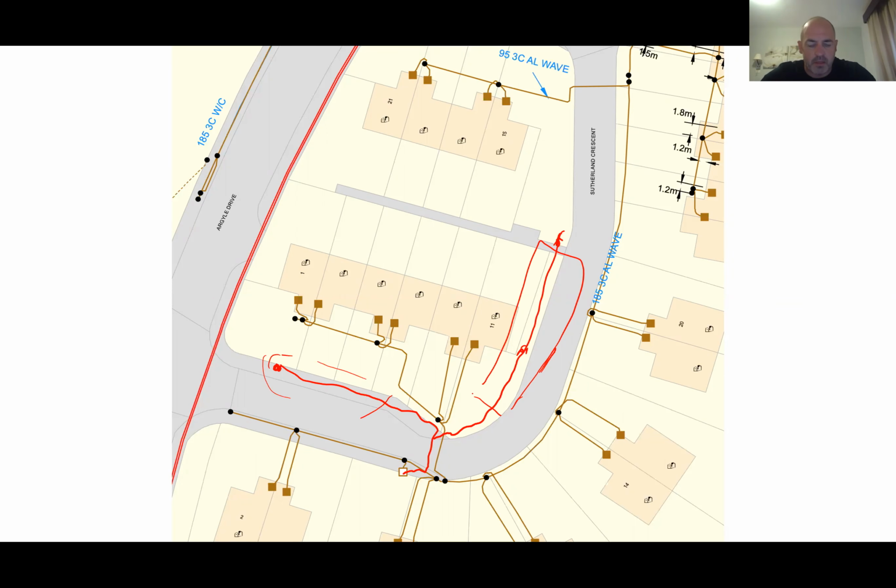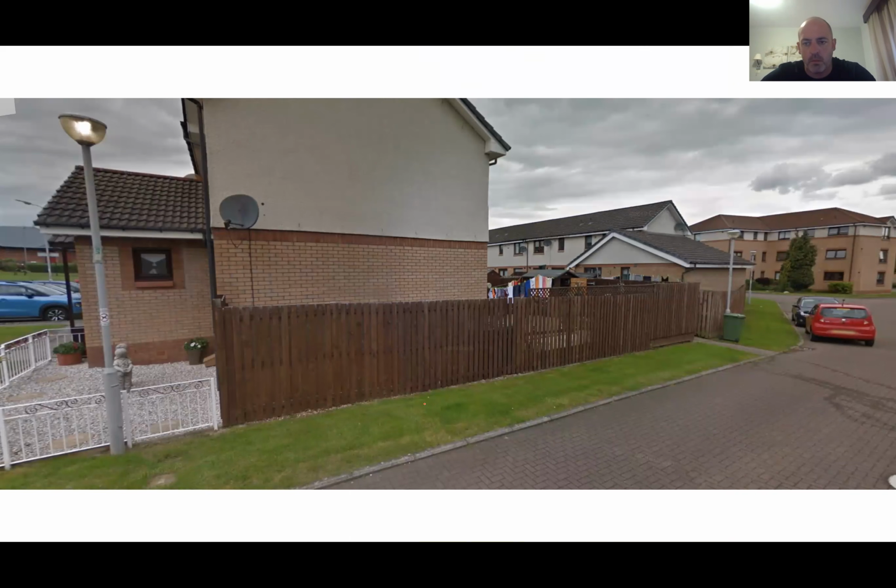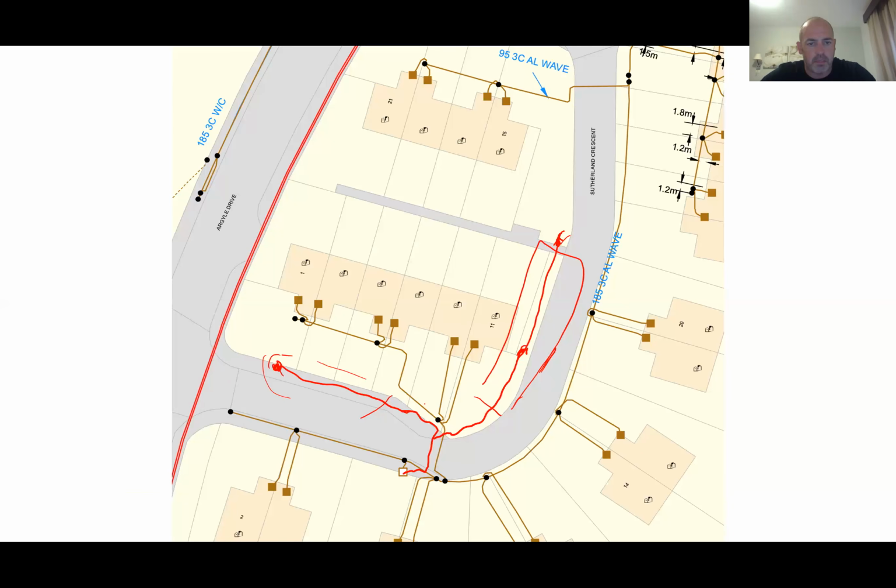And the other thing about this street that's different is we can hook up to all the columns in here, and we generally only get the lighting network. You do get some signal going back to the pillar and down the LV, but this street, to find everything in the house connections, takes more work, because you'll also notice in this street, the more modern houses, they use a PME system, which has a lack of an earth at the property end. So it's very difficult to get signal to run down here to these buildings. What we have to do is hook up and trace back in a lot of cases to find them.